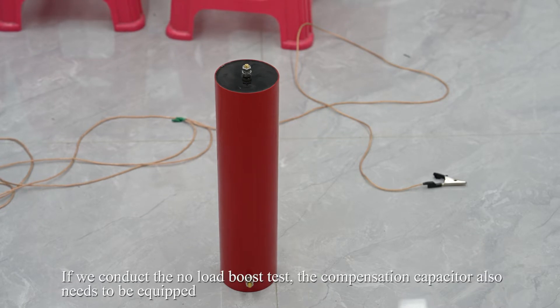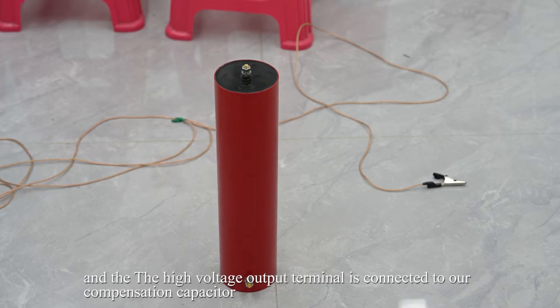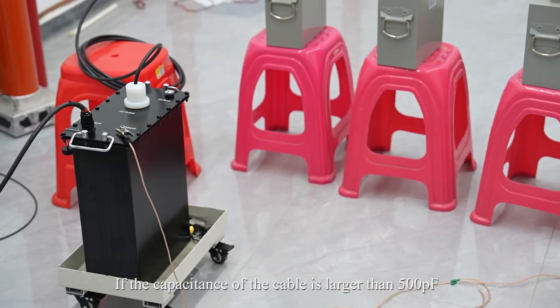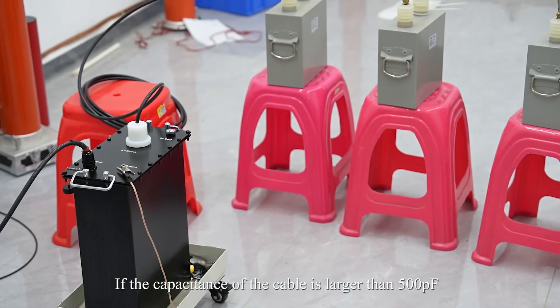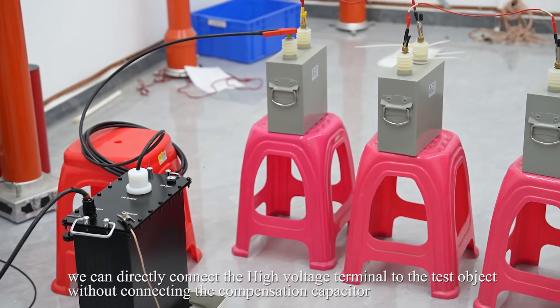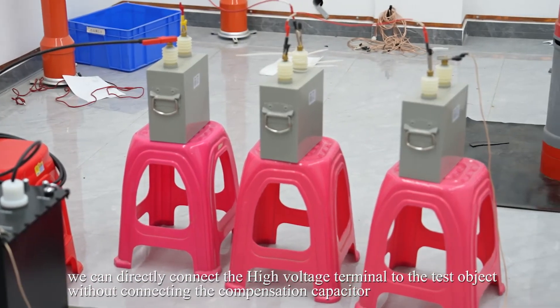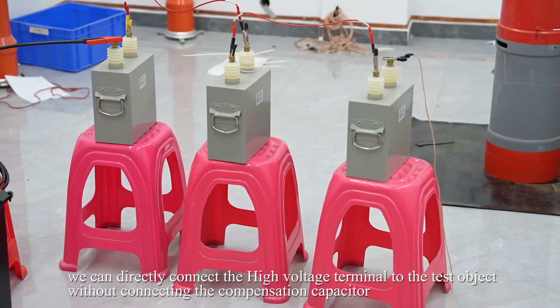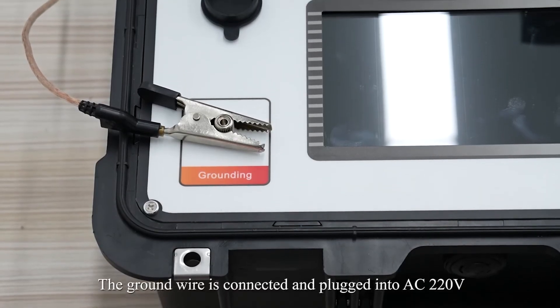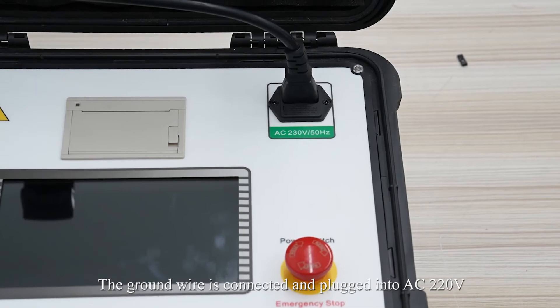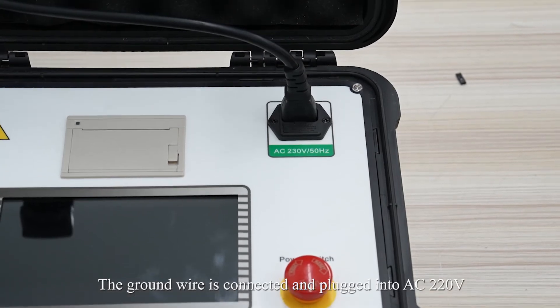If we conduct the no load boost test, the compensation capacitor also needs to be equipped, and the high-voltage output terminal is connected to our compensation capacitor. If the capacitance of the cable is larger than 500 pF, we shall directly connect the high-voltage terminal to the test object without connecting the compensation capacitor. The ground wire is connected and plugged into AC 220V power.